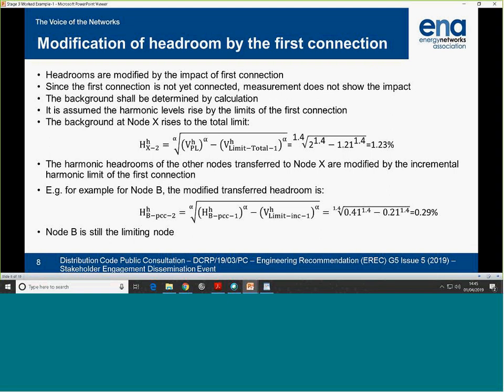Concurrent connection at the same PCC. The connection is a 2000 MVA connection. That means that at point X, still point X, K1, according to the apportionment curve, is 0.66. I assume that for the second connection, the background at X has risen to the total limit of the first connection. The room available for the second connection is the total limit of the first minus the planning level. That's the new headroom.